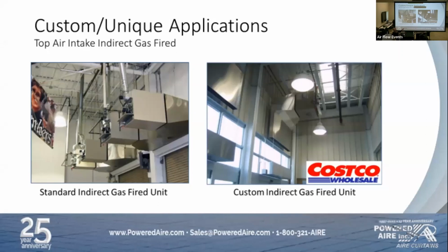This is kind of slick. So we do a lot of work with Costco. We do their beer caves, we do their entry doors. They were originally using electrically heated units. They wanted to switch to indirect gas fired. This is a standard indirect gas fired unit. You have your air curtain, your transitions, and then your indirect gas heaters. This is what Costco has. They were going with this design, but it's big. They're big and bulky, and it's not a pretty air curtain. It was blocking all of this natural light coming in through the glass transom.